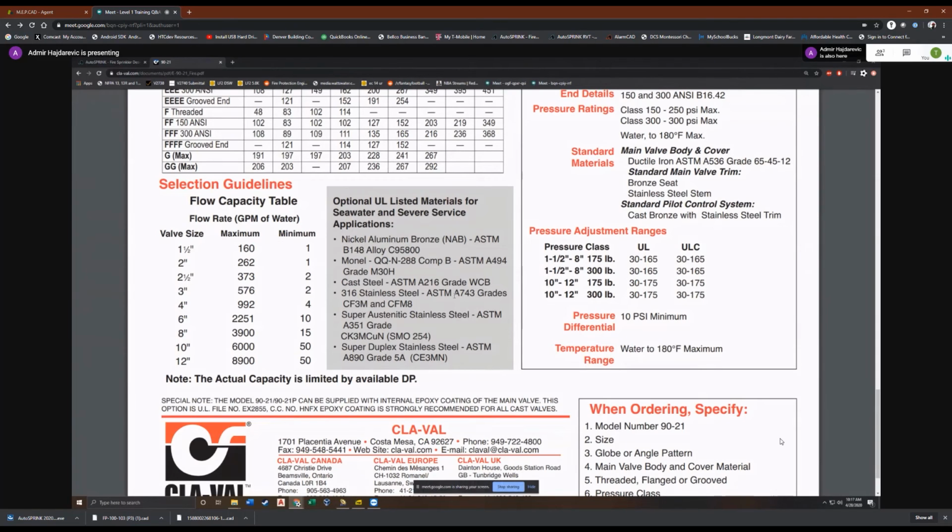It functions like any other valve, where we basically specify a pressure loss or resistance through the device. So can I set the pressure losses, do the math in my head from the pump outlet, and set the losses, 10 psi, 10 psi or whatever, to get down to under 150? Yeah, absolutely. If you've got 200 psi output on your pump at 500 GPM, then you could do 25 and 25 to account for a 50 psi loss, so that downstream of those PRVs you've only got 150.